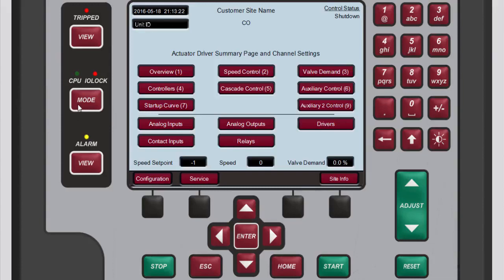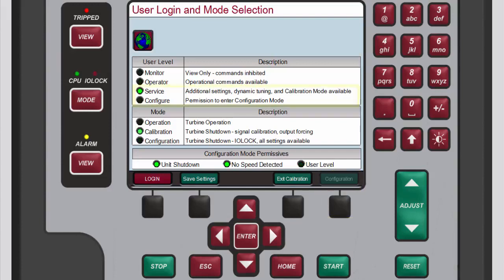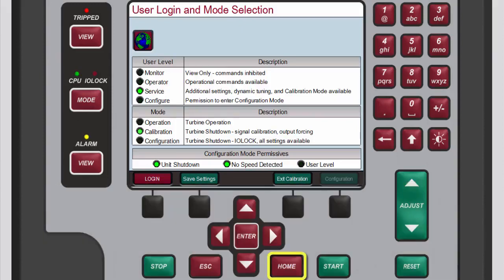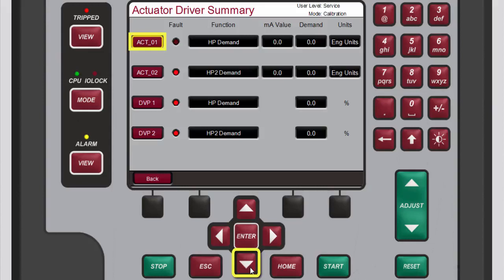To calibrate the actuator drivers you must be in calibration mode, so you need to exit configuration mode, log into either the service or configure user level, and then put the 505 into calibration mode. Refer to the changing user levels and changing modes and languages tutorials to learn how to do this. After you are done, return to the main screen, then return to the actuator 1 screen by selecting drivers and then selecting actuator 1.